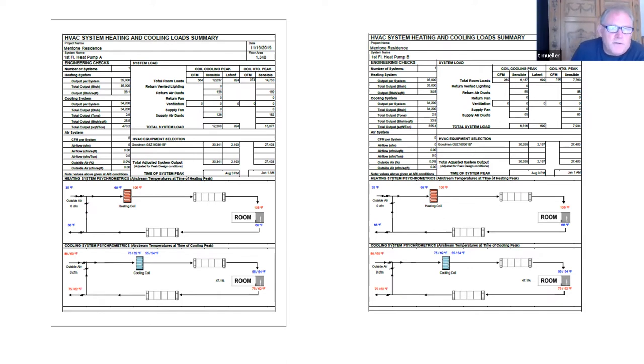In this case, it's a cooling load dominated climate, and the cooling loads are about 30,000 BTUs per zone, which is about 2.5 tons. So we put in 2-ton systems to completely top out the heat pump capacities and increase the efficiency, or have the efficiencies be as high as possible.